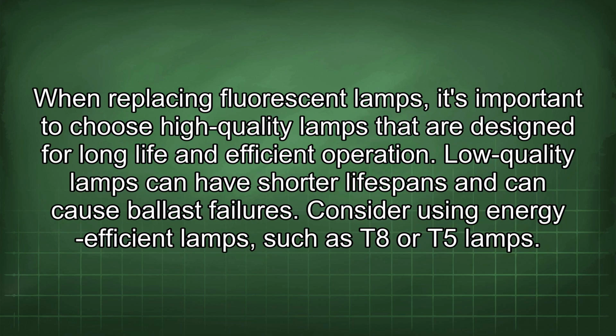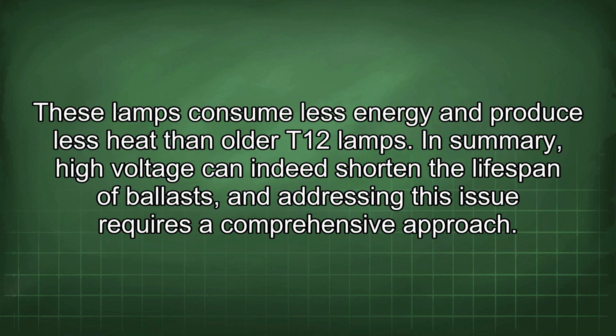When replacing fluorescent lamps, it's important to choose high-quality lamps that are designed for long life and efficient operation. Low-quality lamps can have shorter lifespans and can cause ballast failures. Consider using energy-efficient lamps, such as T8 or T5 lamps. These lamps consume less energy and produce less heat than older T12 lamps.